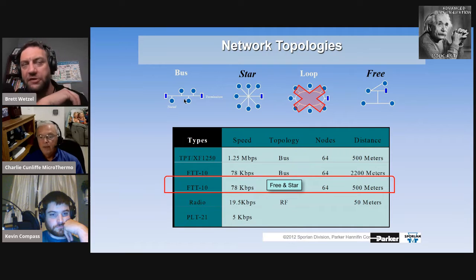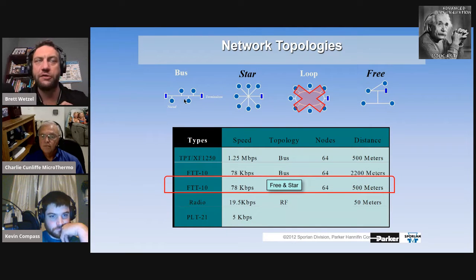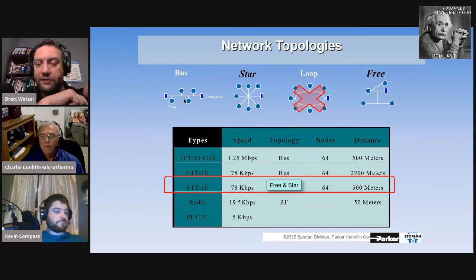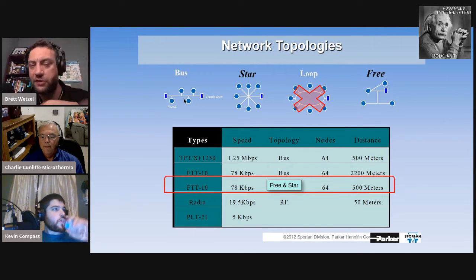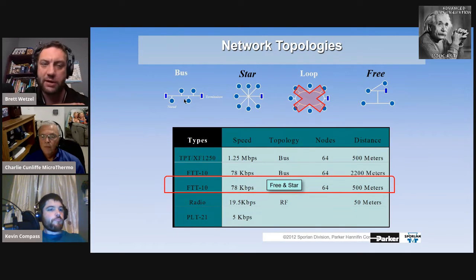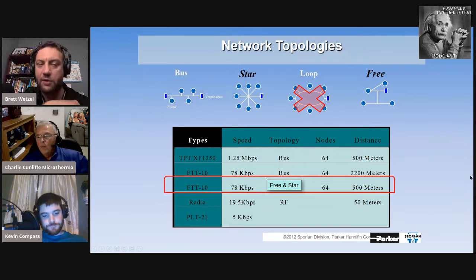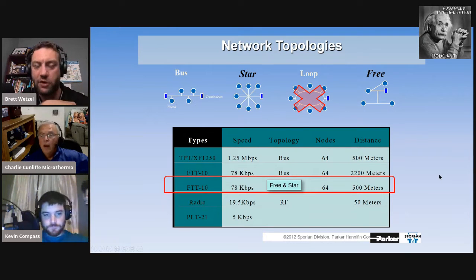Does that limit you to what you can connect to, or does most equipment have the capability? Like if you take a NIDEC drive and want to communicate with it, they have different plugins you can plug in, so you can make it communicate via IP or BACnet or Modbus. It all depends on what card you have.